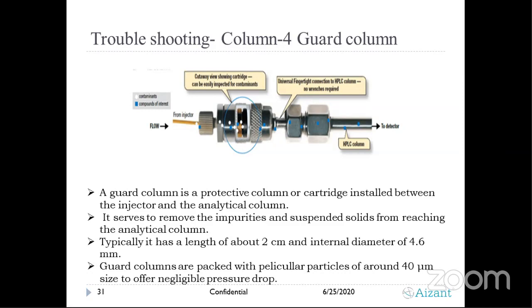If you're using matrix samples with a high load of excipients, this will protect. So your main column will be protected, the frit will be protected, and you can use the main column for a longer time. The guard column can be replaced based on the methodology, after 15 sets of analysis or 20 sets, but your main column will be protected.